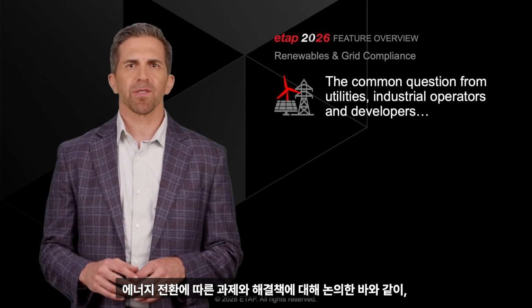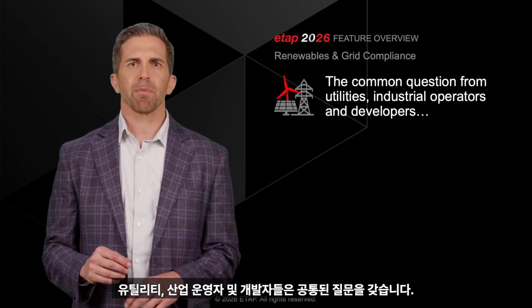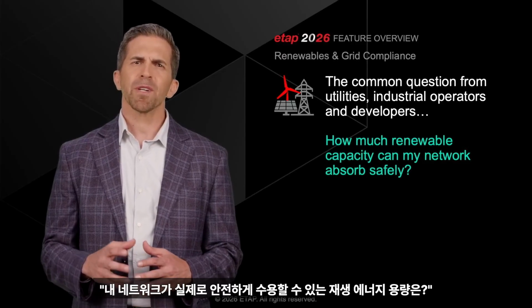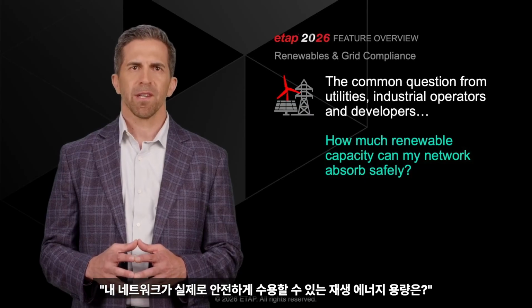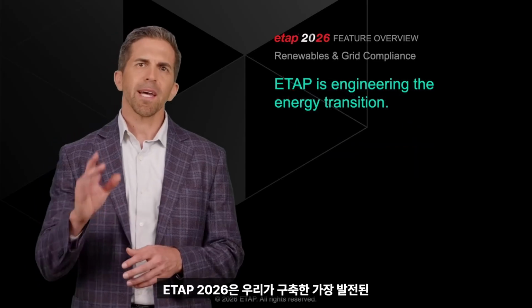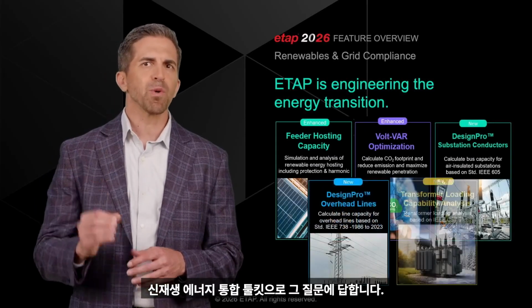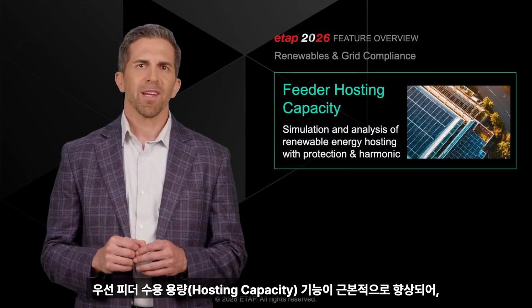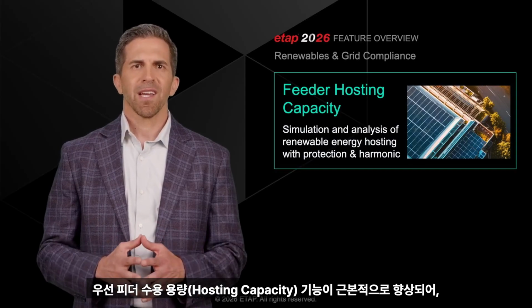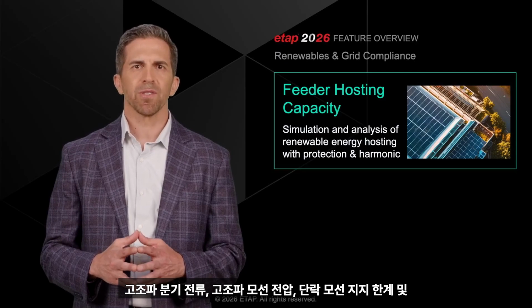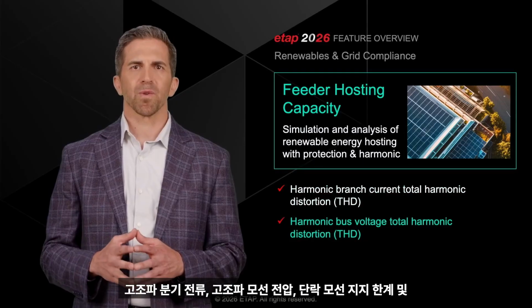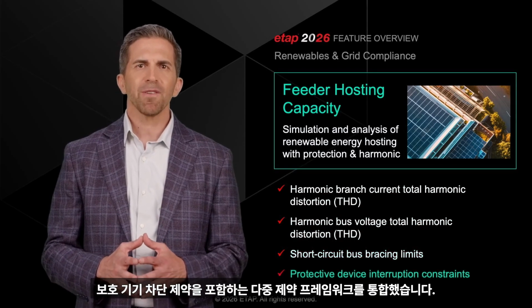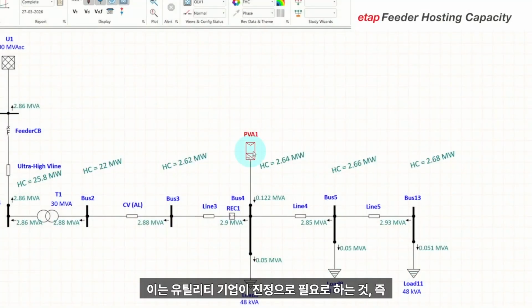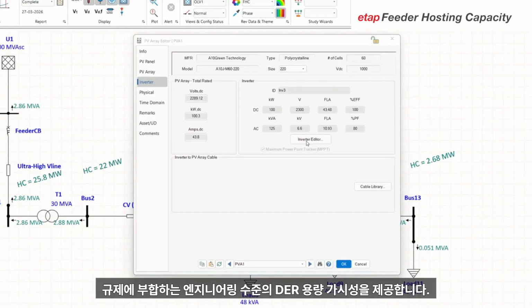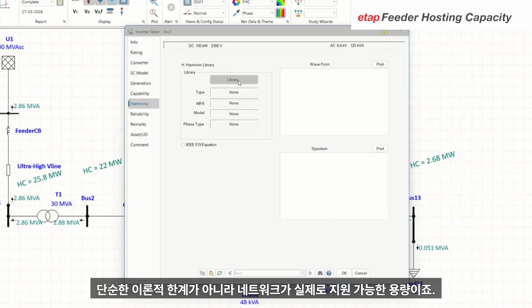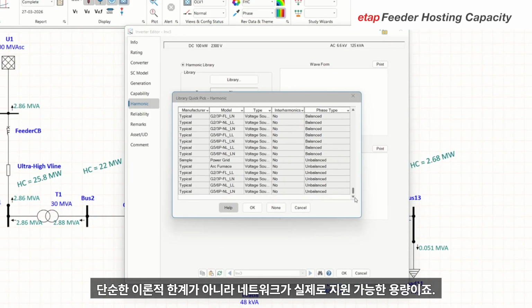As we have discussed some of the challenges and solutions with the energy transition, utilities, industrial operators, and developers have a common question. How much renewable capacity can my network actually absorb safely, while ensuring compliance with these standards? ETAP 2026 answers that question with the most advanced renewable integration toolkit we have ever built. To start with, feeder hosting capacity has been fundamentally enhanced, incorporating a richer, multi-constraint framework that includes harmonic branch current, harmonic bus voltage, short-circuit bus bracing limits, and protective device interruption constraints. This delivers what utilities truly need: a regulation-ready, engineering-grade view of DER capacity. Not just theoretical limits, but what the network can actually support.